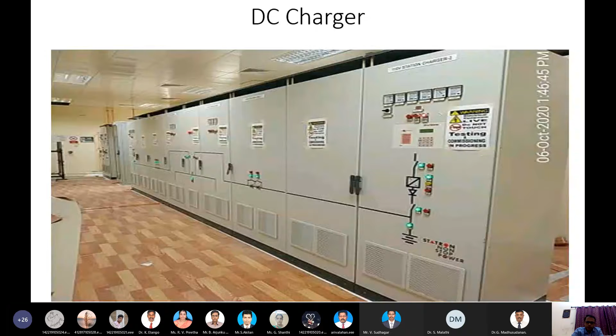This charger is a feeder for the battery substation, and in case something goes wrong, the battery will take care of the supply for the complete substation's utilities. The safety measures or possible hazards are fire, flashover, and other fire-related hazards. The room has fire sensors, and the purging system is nitrogen.